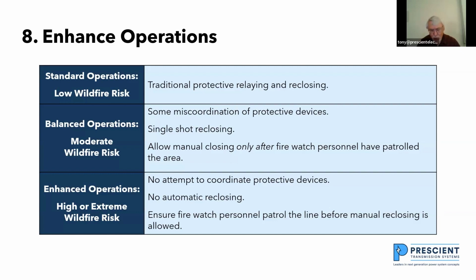I don't have any coordination on that line, and I'm not going to allow automatic reclosing because I'm in enhanced operations, high wildfire risk. I know I've got high temperature. I know I've got low humidity. I've got days without rain. And now I've got high winds that could be blowing trees over.